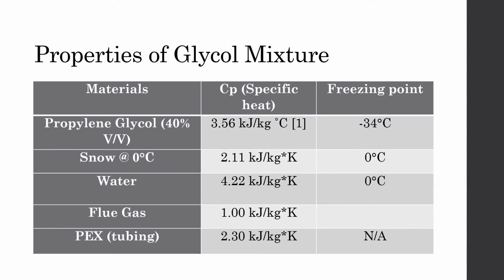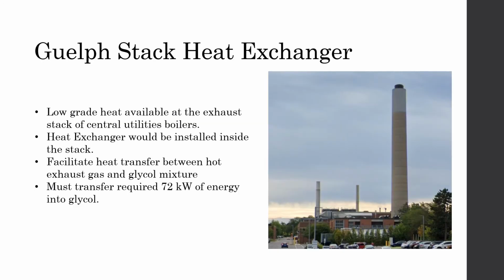It was chosen due to its low freezing point, relatively high specific heating value, its non-toxic properties, and relatively low price when compared to mixtures with higher percentage of propylene glycol. The University of Guelph campus has many pre-existing heat sources that can be used to provide the necessary heat energy for the proposed hydronic system.